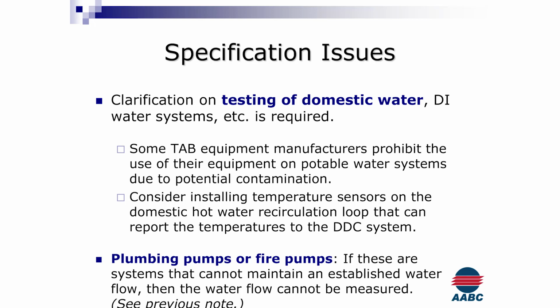Clarification on testing of domestic water. This is something new, and actually AABC just came out with a standard for testing domestic water. Personally, on my end, we do it with an ultrasonic meter. I do not like the liability of plugging any of my meters in, even if I've cleaned them, to any potable water systems. It's just an inherent risk, and I would advise anybody against it personally. But there is a new standard that will allow us to go through, clean our meters, and actually plug into the probes if we need to.